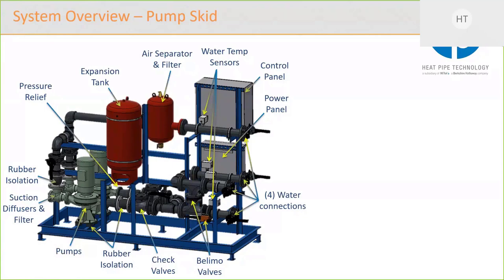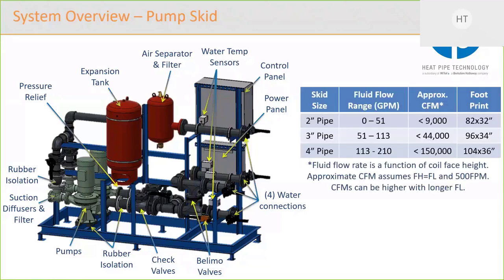Now, I'm not going to go through every component on there, but I just wanted to show you this picture so you could see that basically the whole system minus the coils is on this skid. So you have a module that you can install into your building. What we do is we size our module based on the flow rate. It's actually limited by the air separator. So the 2-inch, 3-inch, and 4-inch refers to the pipe diameter that we normally use on the skid and that connects the skid to the coils. And you can see the varying gallons per minute that those skids will provide.